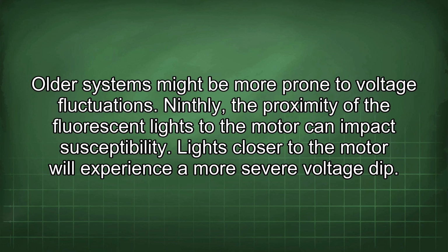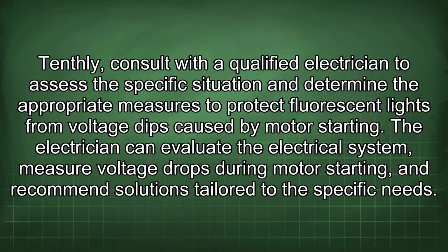Ninthly, the proximity of the fluorescent lights to the motor can impact susceptibility. Lights closer to the motor will experience a more severe voltage dip. Tenthly, consult with a qualified electrician to assess the specific situation and determine the appropriate measures to protect fluorescent lights from voltage dips caused by motor starting.